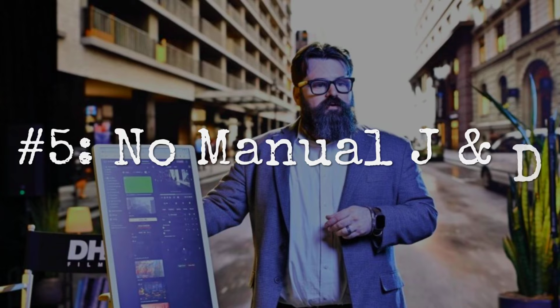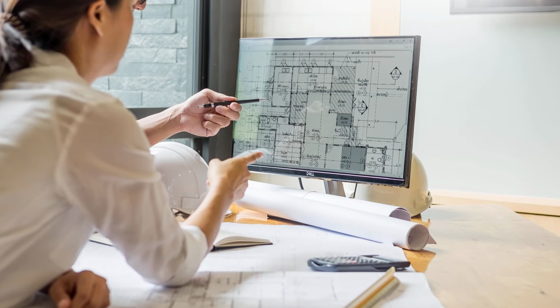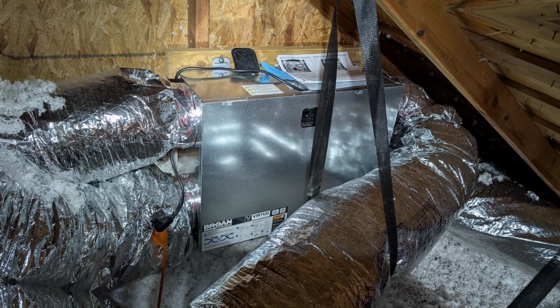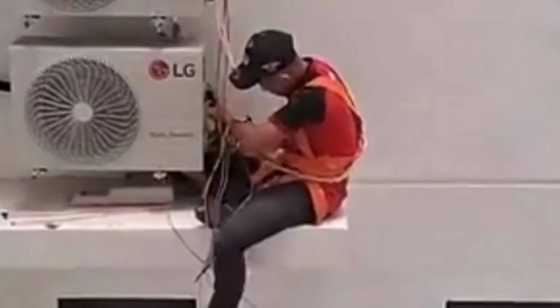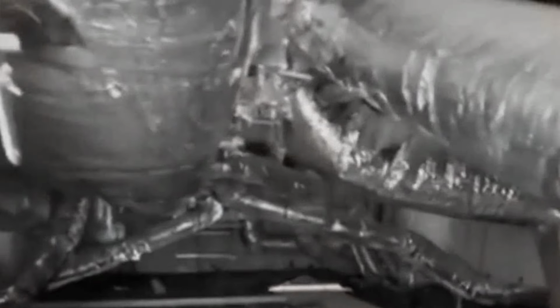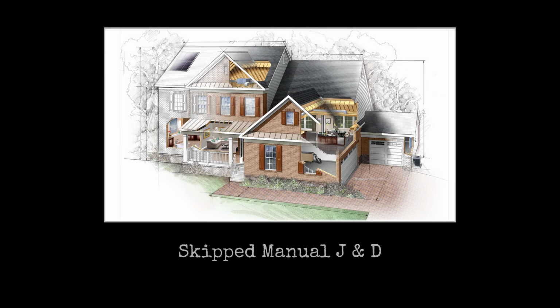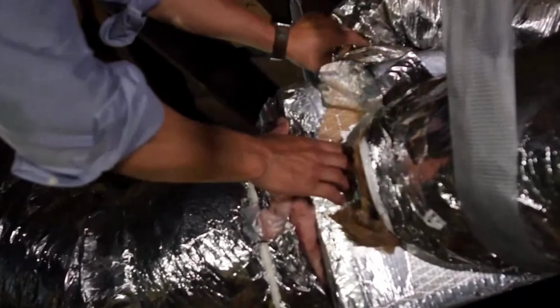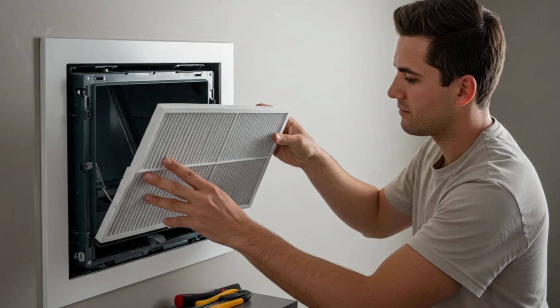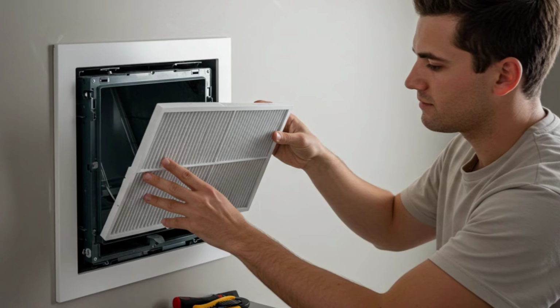That was number 4, and at number 5, an HVAC system installed without engineering: no Manual J load calculation, no Manual D duct design, no airflow verification after installation. This is the root cause behind every other problem on this list. They oversized it and it's bad. The ductwork, the missing returns, all of it traces back to this.